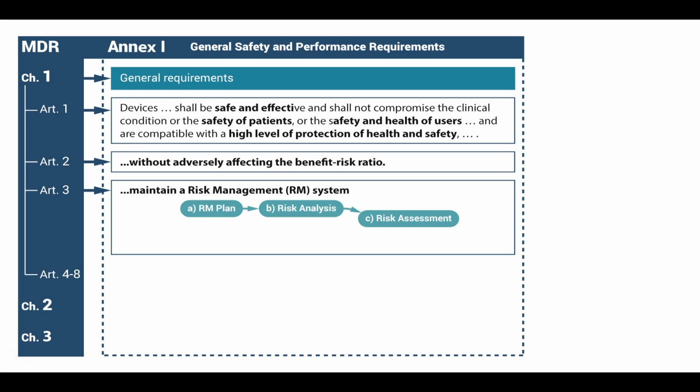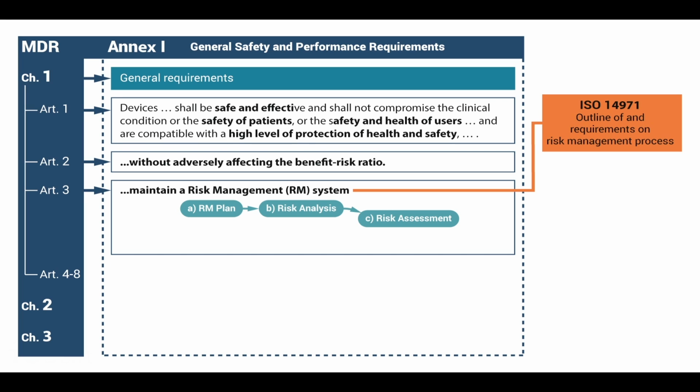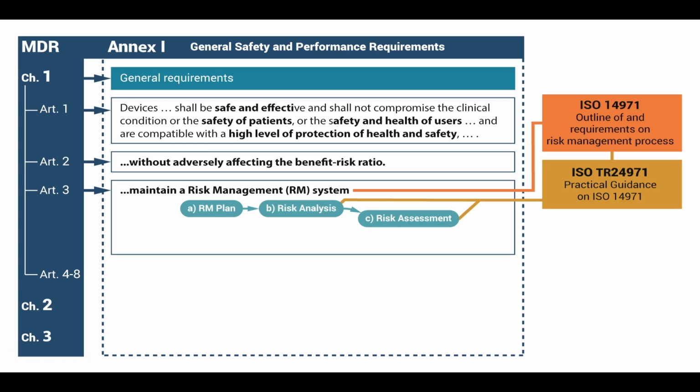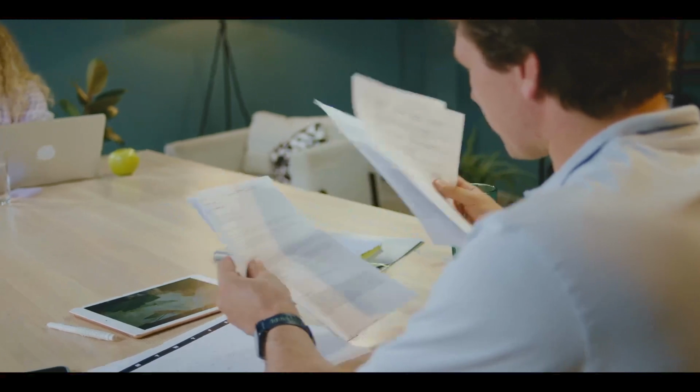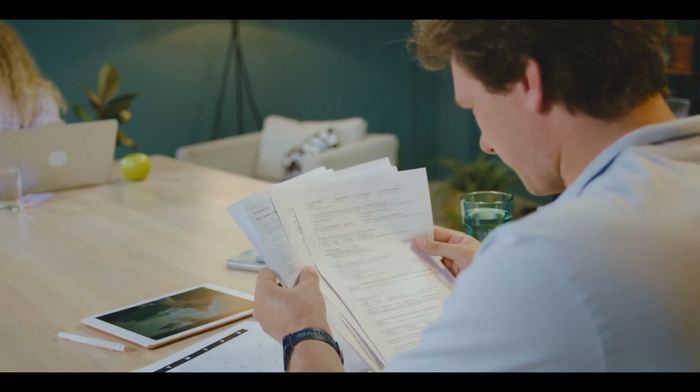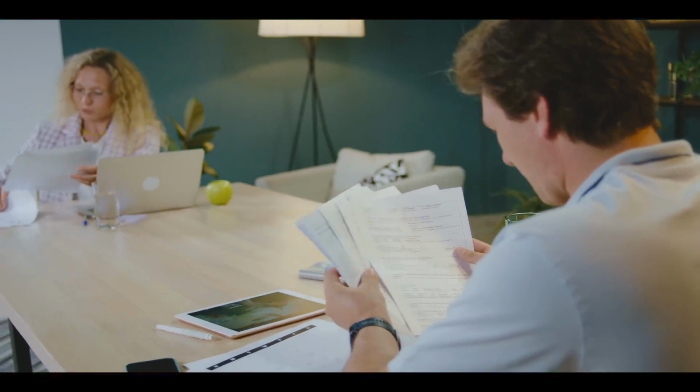You don't have to develop your own approach for that, because how this risk analysis and assessment should be shaped is extensively described in ISO standard 14971. And to help you even more, there's a practical guidance document, ISO TR 24971, which explains all the terms, concepts, and approaches that you need so you can follow ISO 14971. We will extensively treat these later.